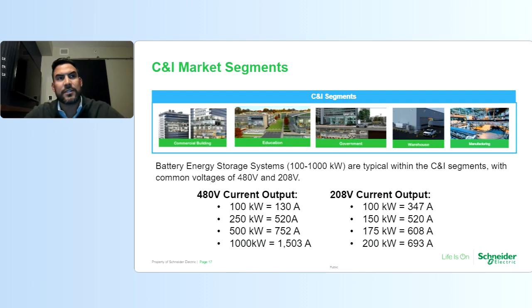Because when you're designing your system and you want to use an energy storage system for emergency power, you want to connect that to some sort of panel board or switchboard where you have those loads already isolated, and make sure that you're sizing your equipment correctly, right? You don't want to oversize your main switchboard to have your energy storage system, your utility, and your PV system, because then you go from a 1600 amp or 2000 amp switchboard to a 4000 amp switchboard. So it's really important to keep in mind these current ratings and power ratings of these energy storage systems, so you're sizing your system correctly.